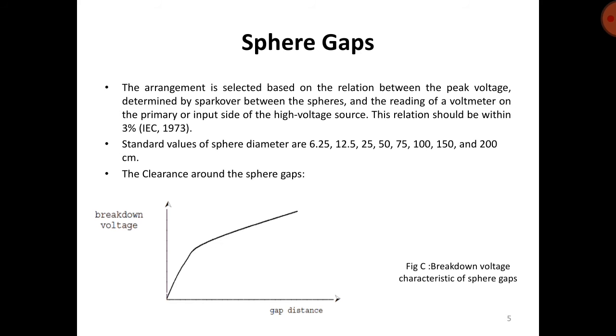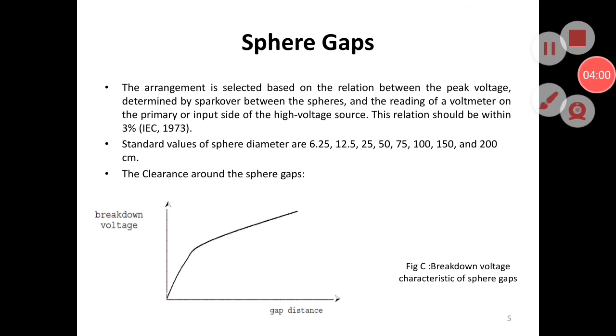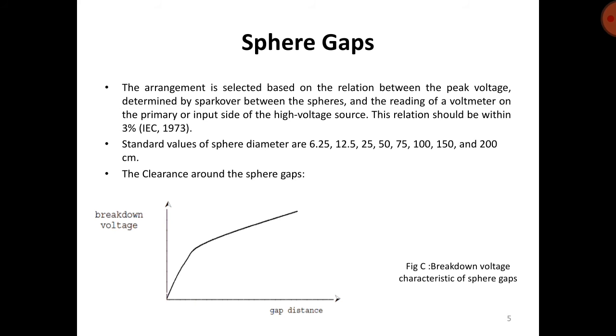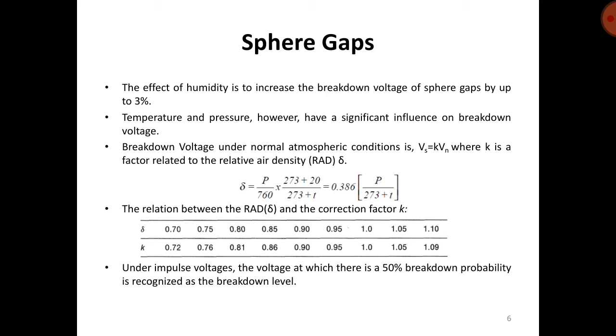The clearance around the sphere gaps. There must be clearance around the sphere gaps as per the guidelines given by the international committee. Here we can see the graph. This graph is for the breakdown voltage characteristics of a sphere gap. We can see that as the gap distance increases, the breakdown voltage also increases. So this is the characteristic of the sphere gap arrangement. The effect of humidity is to increase the breakdown voltage of sphere gaps by up to 3%. So this is the effect of humidity in sphere gap measurement.